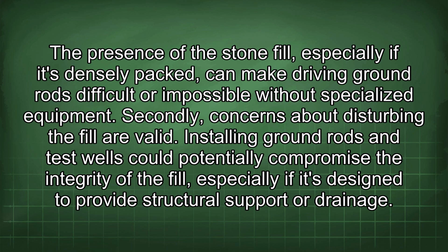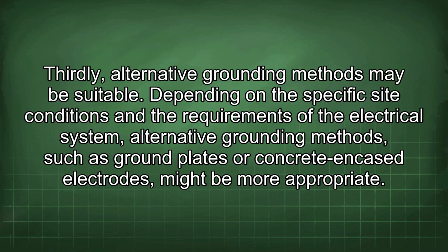Installing ground rods and test wells could potentially compromise the integrity of the fill, especially if it's designed to provide structural support or drainage. Thirdly, alternative grounding methods may be suitable. Depending on the specific site conditions and the requirements of the electrical system, alternative grounding methods such as ground plates or concrete-encased electrodes might be more appropriate.